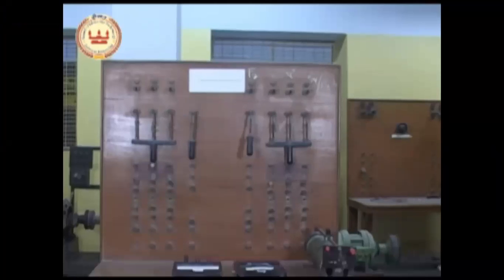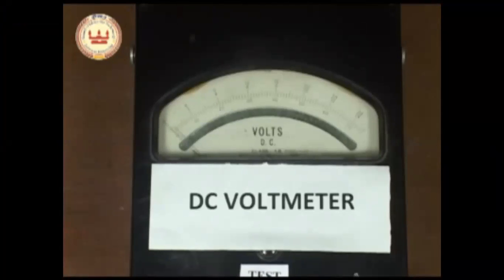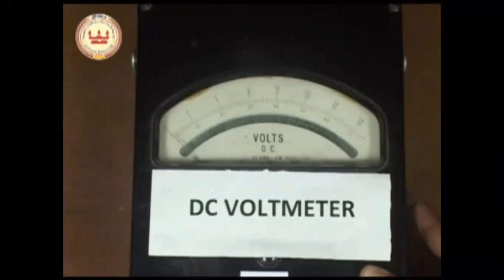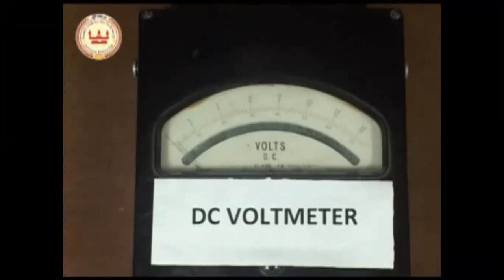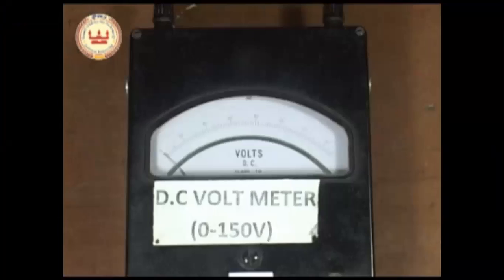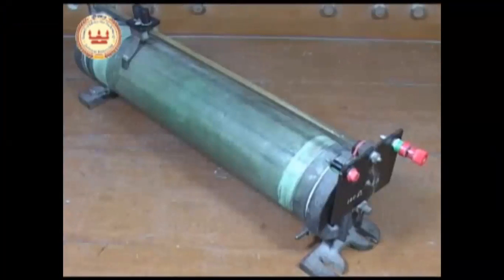Calibration of voltmeter. In this experiment, we should use these instruments. This is a DC voltmeter of range 0 to 75, and next one is the voltmeter 0 to 150 volt DC, and this is the rheostat of 100 ohm and 5 ampere rating. The rheostat will be connected as a potential divider.